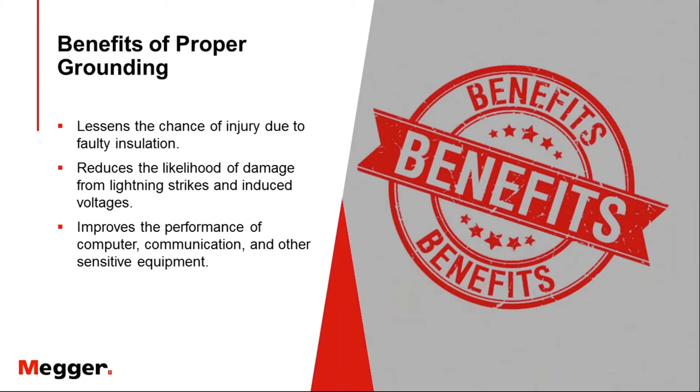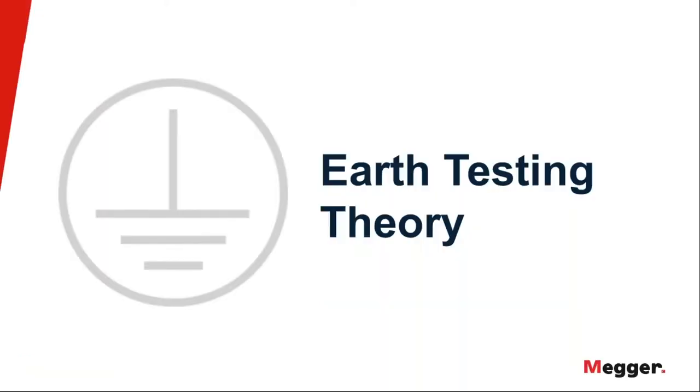Some other things that people don't think so much about: static. Operation of machinery can build up static charges. A belt moving in a motor can create a separation of charge. You want to have a good grounding system in place so that anything of that sort will just go into the ground. Finally, things like basically noise from your office equipment and complex process control equipment.